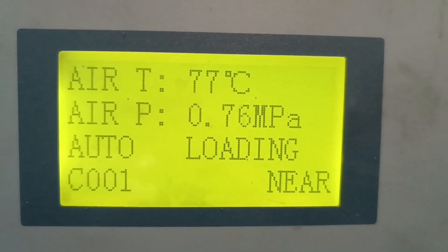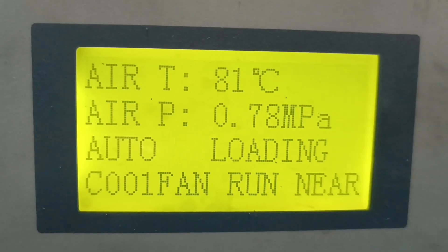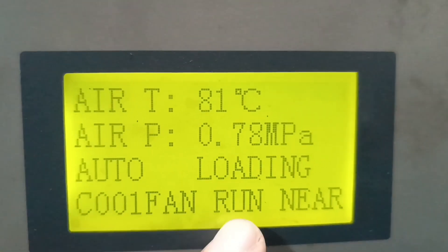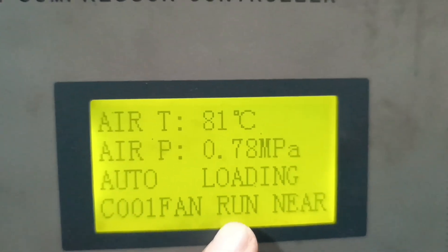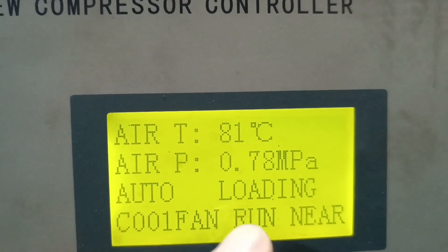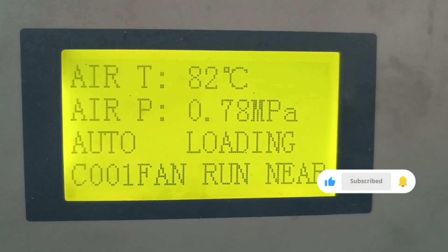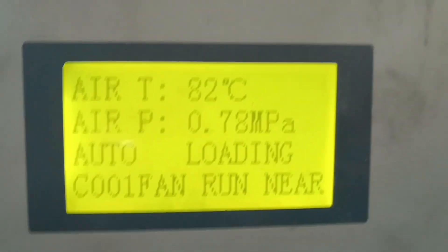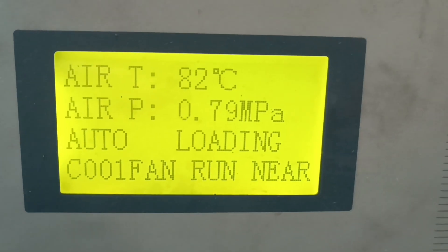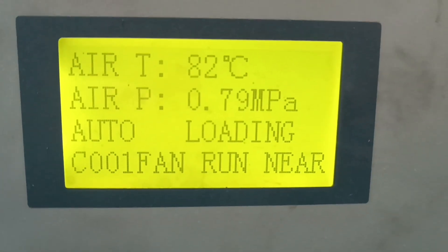As the temperature increases — when air temperature reaches 80 degrees centigrade, the fan automatically starts running. You can see the fan running in the picture at the bottom because the temperature is close to 80°C. When the temperature drops back below 75 degrees, the fan automatically stops — you can see this in the picture.